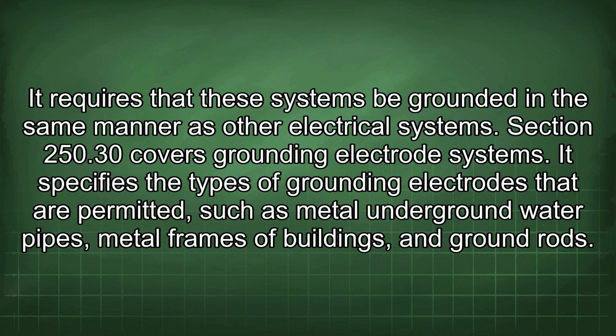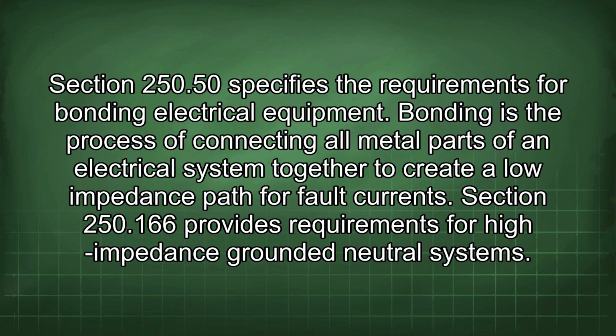It specifies the types of grounding electrodes that are permitted, such as metal underground water pipes, metal frames of buildings, and ground rods. Section 250.50 specifies the requirements for bonding electrical equipment. Bonding is the process of connecting all metal parts of an electrical system together to create a low-impedance path for fault currents.